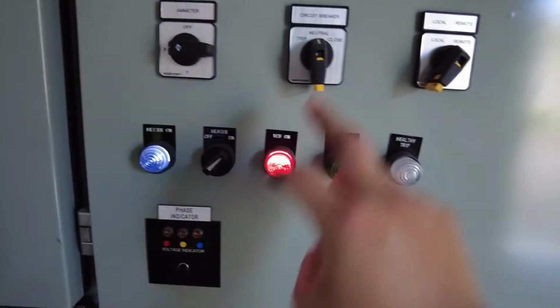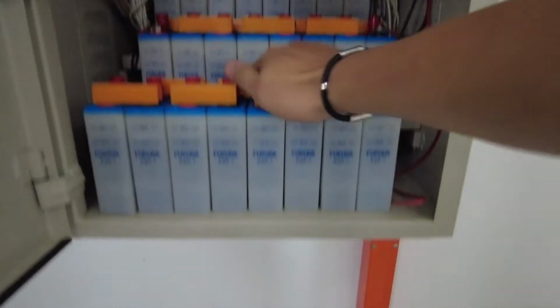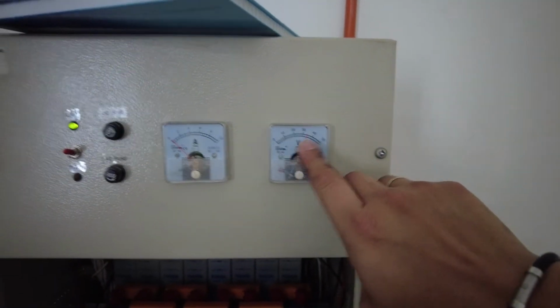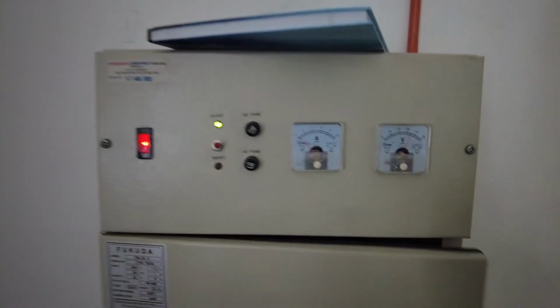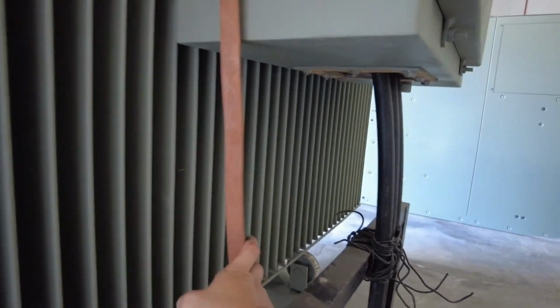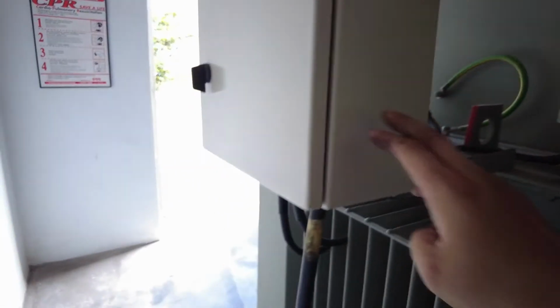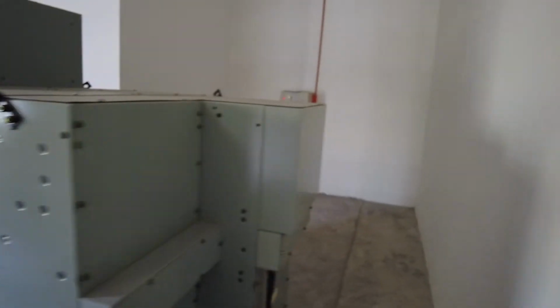This is the incomer panel, and here we have the transformer feeder. Indicator light okay, heater okay, in good condition. Okay, let's check the tripping unit. Okay, tripping unit, water level okay, not maximum but not minimum yet. Okay, voltage is okay, charging amp is okay, under float condition. No sign of overcharging. The room is dry, no water, no moisture, no storage. Earthing okay, earthing is okay. Cover is okay. All panels are closed, no panel is open.